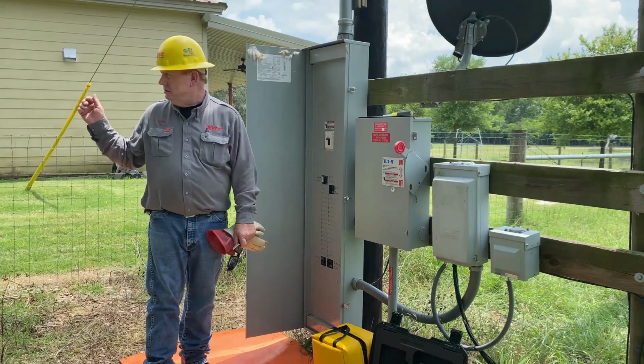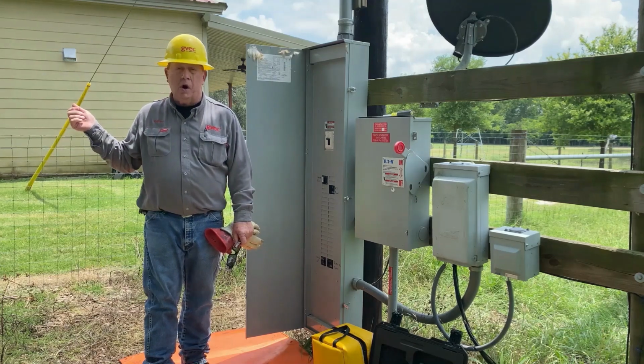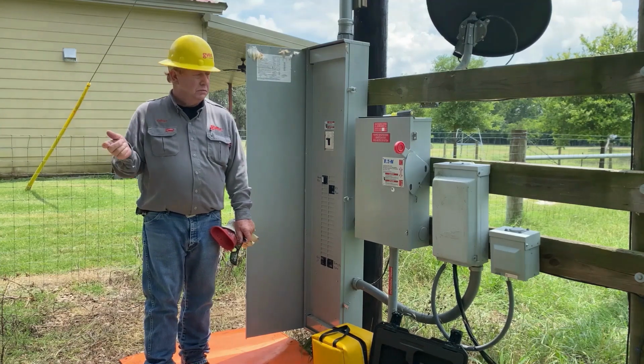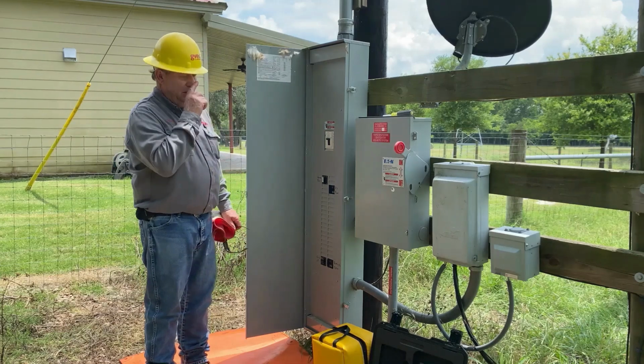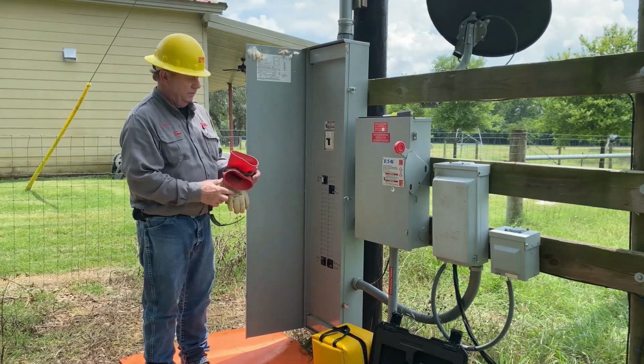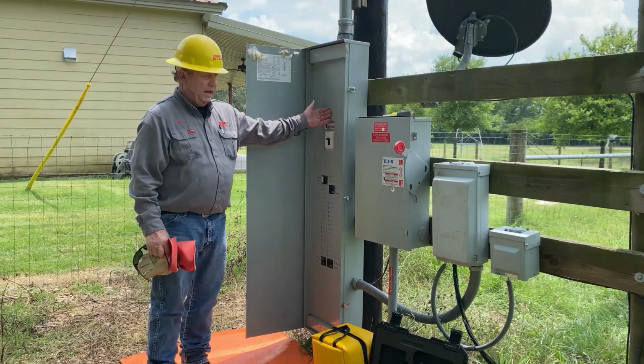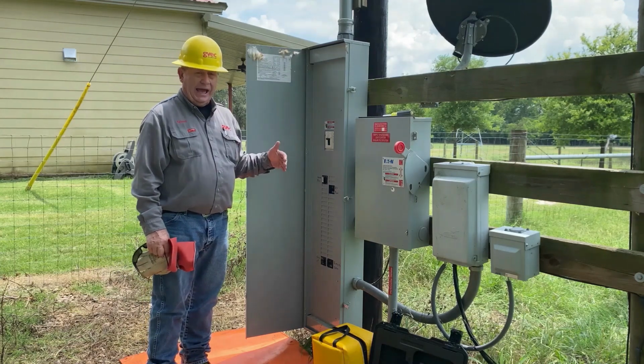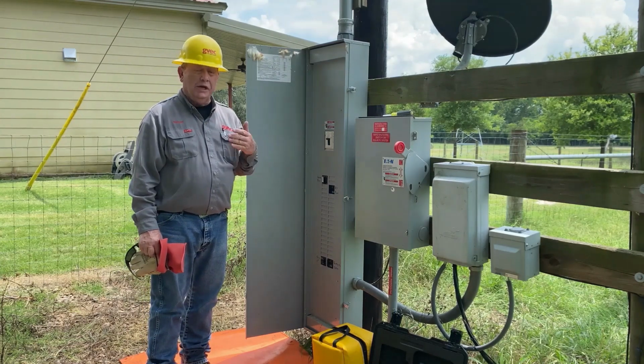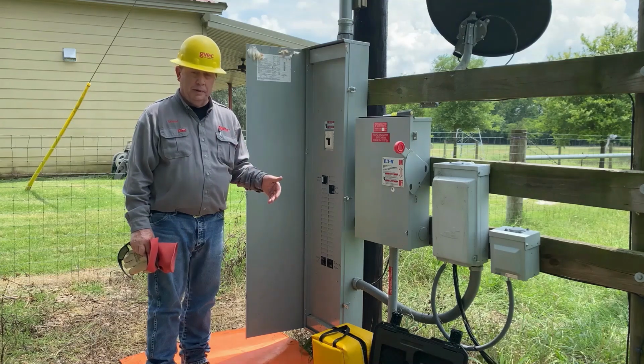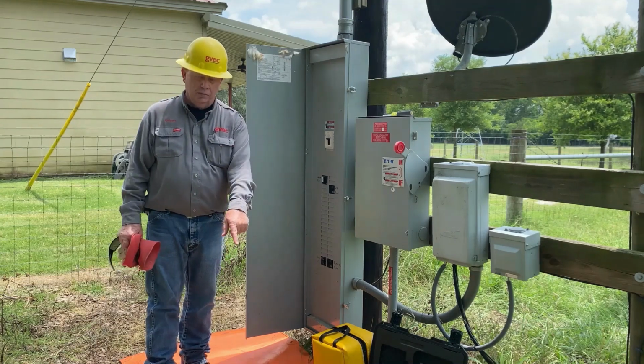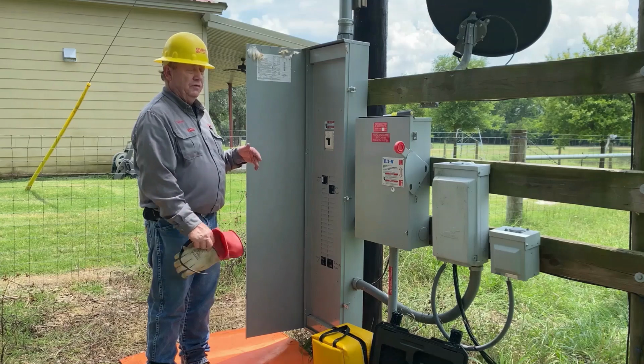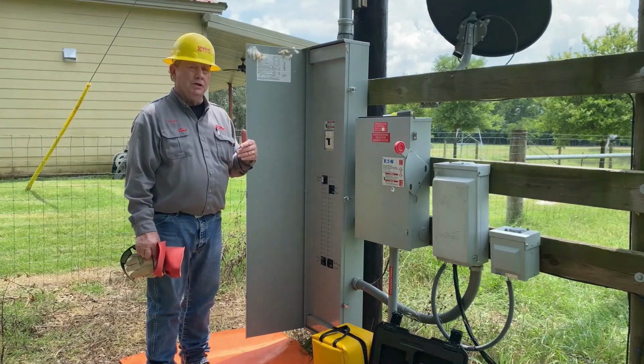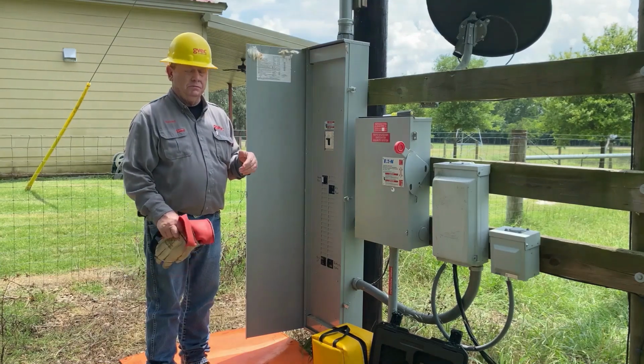He has a Tesla Powerwall feeding back into the grid. So what we're going to do today is remove the panel cover and add an exterior load that we control. We have a Super Beast and we have an external load box, and we'll set that up at 240 and let it cook while we monitor with thermal imaging.